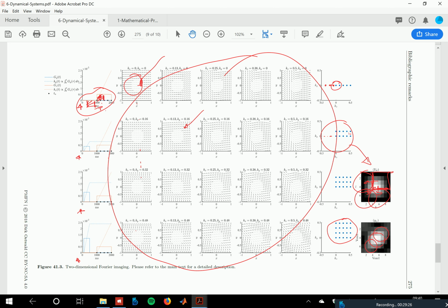Once and for all doesn't quite work, because it depends on the sequence that you use. Whenever you hear somebody say we need a sequence for our experiment, the sequence is a protocol or program that says when Z gradients are turned on, when excitation pulses are sent, when X gradients are turned on, when Y gradients are turned on and off, and when the data is acquired.